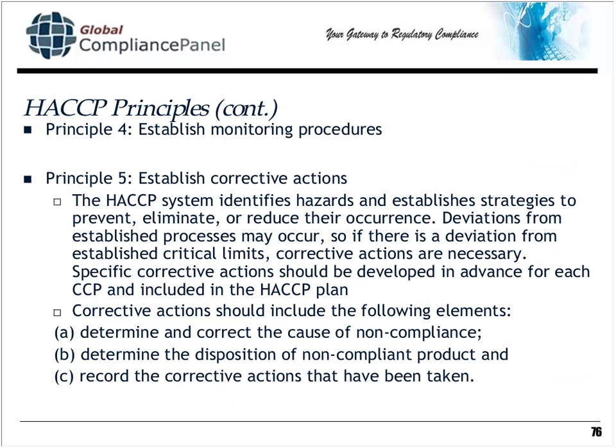Principle number 5, we're going to establish corrective actions. And this is one thing that I really like. You're going to do this analysis, and you're going to put a corrective action in place in advance. So you're going to think about what corrections and corrective actions you're going to put in place before the problem happens. And oftentimes in device manufacturing QMSs, I don't see people take this approach. But here, you develop a list of all of the corrections and corrective actions based upon the analysis. You're ready to go when one of these things happens.